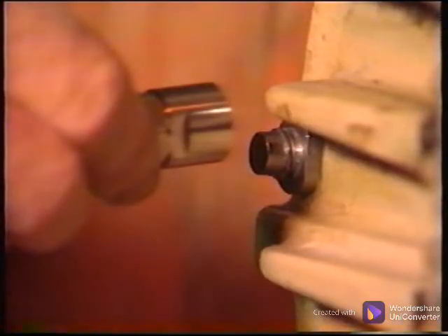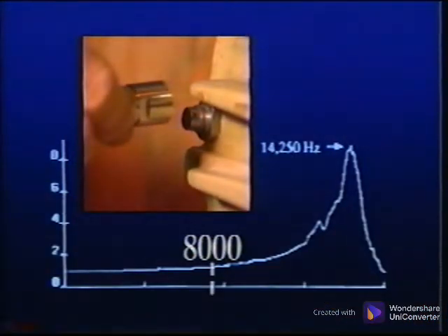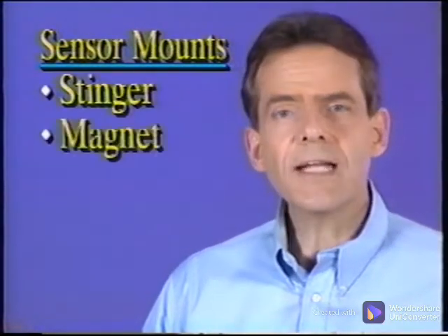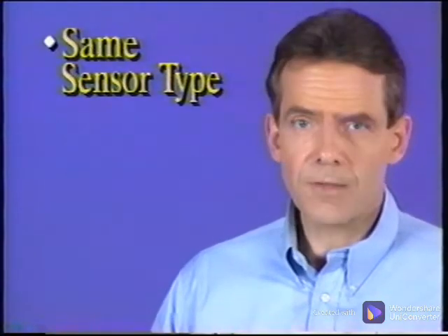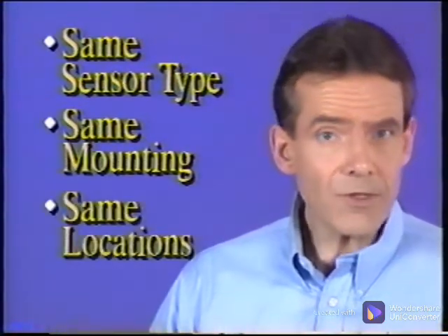This Quick Connect sensor mounting has the benefit of being placed at exactly the same location from one survey to the next, and it goes in place quickly. The response curve is linear over a longer frequency range and even exceeds the magnet mounts. Another method of mounting sensors is to stud mount the sensor in a pre-drilled, pre-tapped hole. This mounting method provides the greatest linear response range and will give the best, most accurate, repeatable data. Whether your sensor mounting is a stinger, magnet, quick connect, or stud mount, collect your data using the same sensor type, the same sensor mounting, and the same locations time after time.